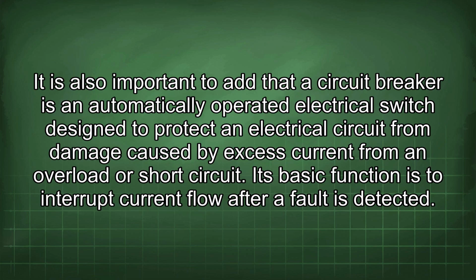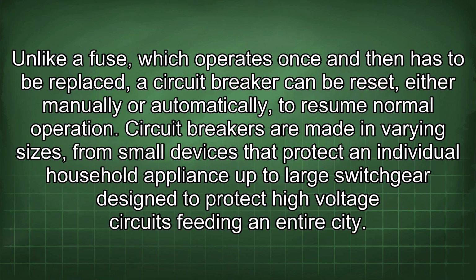It is also important to add that a circuit breaker is an automatically operated electrical switch designed to protect an electrical circuit from damage caused by excess current from an overload or short circuit. Its basic function is to interrupt current flow after a fault is detected. Unlike a fuse, which operates once and then has to be replaced, a circuit breaker can be reset, either manually or automatically, to resume normal operation. Circuit breakers are made in varying sizes, from small devices that protect an individual household appliance up to large switchgear designed to protect high-voltage circuits feeding an entire city.